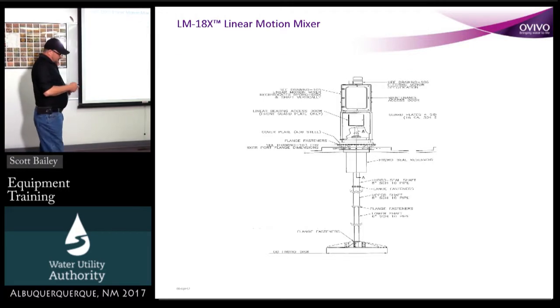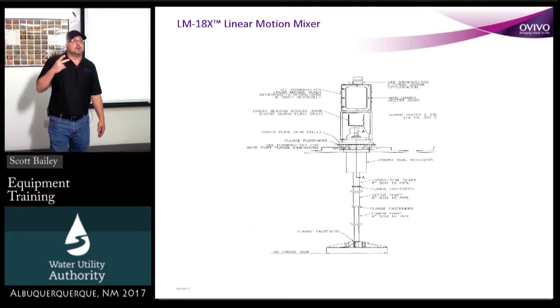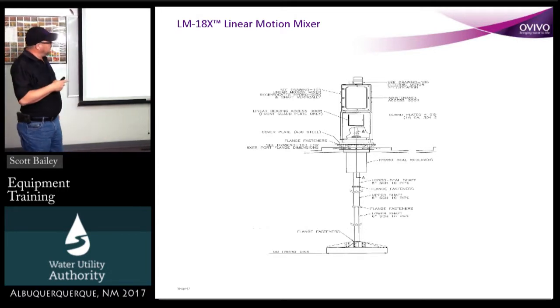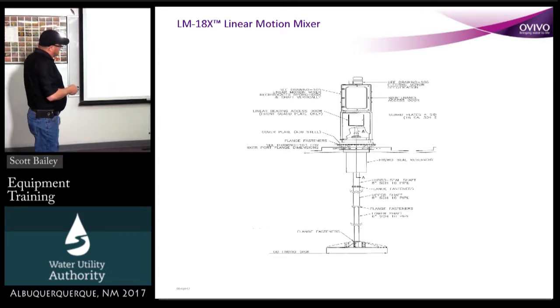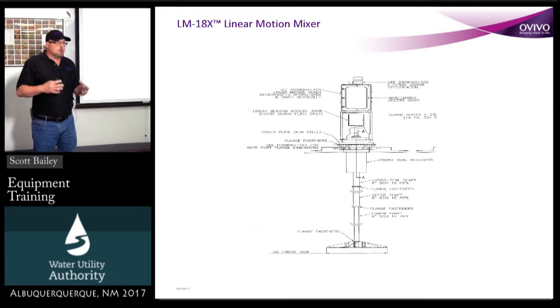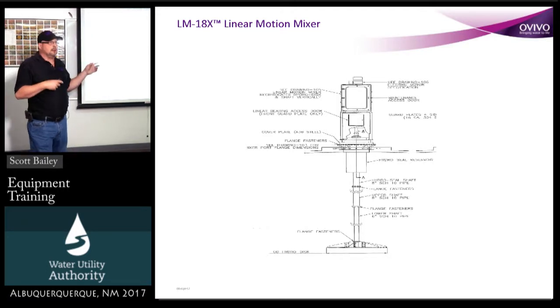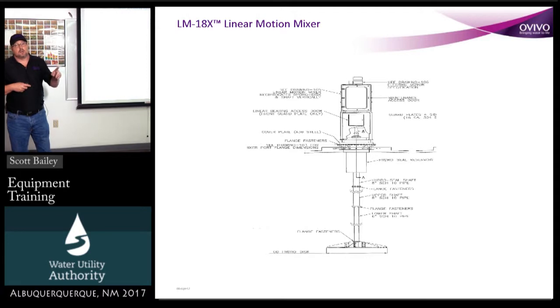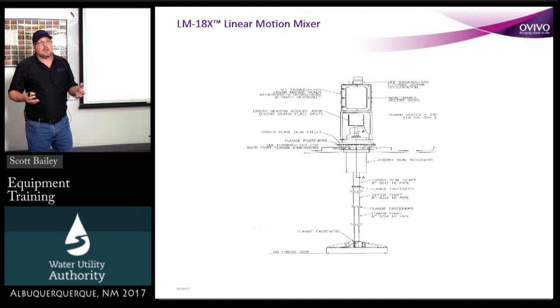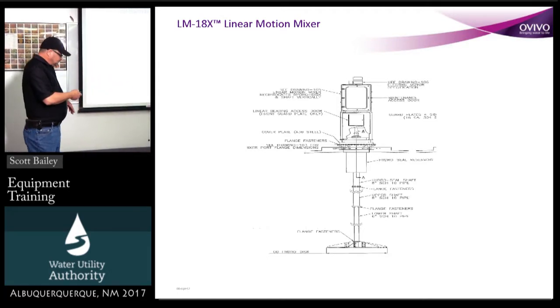In the front of that, you have a little hatch door. The hatch door is there, so you have 2 grease spots in that hatch door, both on the lower bearing. You have a lower bearing that's underneath the cabinet right here. It's a slow moving part, so you don't have a lot of friction, you don't have a lot of heat on the bearing, but it is required for you guys to grease once a week. If you start seeing buildup on the shaft, excess grease, whatever, you can cut it back to like 2 weeks, and we'll get over that in a little bit more.